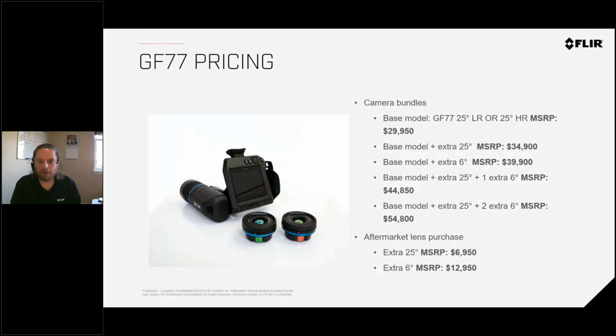So just a little bit of how you would order these. You can order them a la carte. You get the base model camera, and if you want that with a low range lens because you're going to be doing your methane detection, or a high range lens because you're going to be doing your SF6 detection, you can pick which one you want. If you want each, we have an option for that, or a kit built out for that. If you want 3 lenses, all 4 lenses, you can do that. If you buy one lens today and then 6 months from now you find a need for a different lens, you first got the LR lens, now you want the HR lens, you can buy that HR lens 6 months down the road, a year down the road, send your camera in to FLIR, we'll calibrate that new lens to your camera, and then you'll have 2 operating lenses with your camera. So you can definitely make aftermarket purchases to build onto your portfolio.